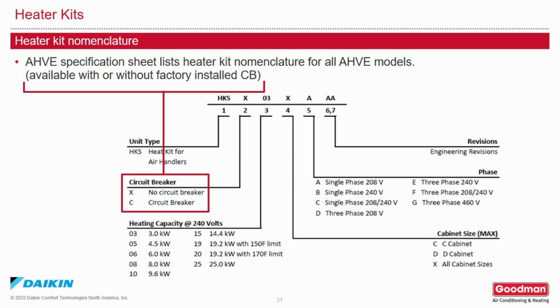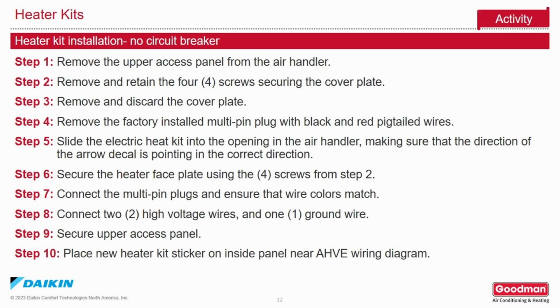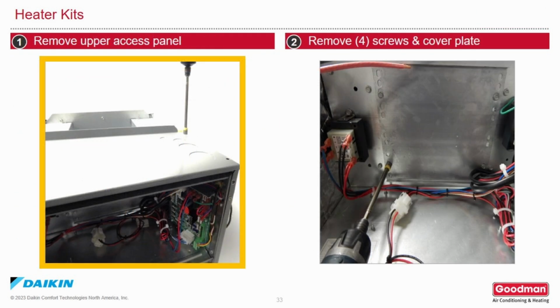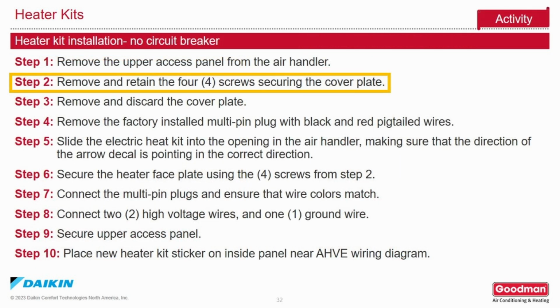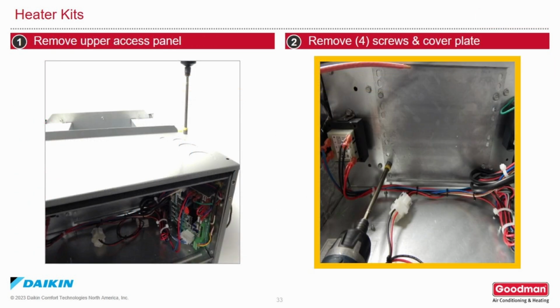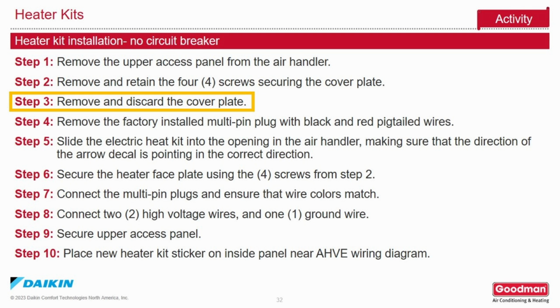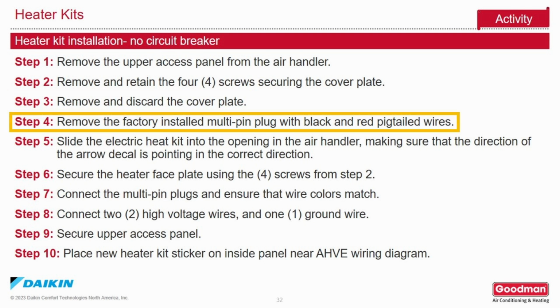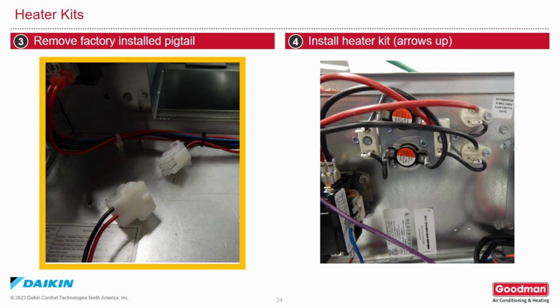Here's an example of the heater kit nomenclature. The specification sheet lists the heater kit nomenclature for all AHVE models. They are available with or without a factory installed circuit breaker. Heater kit installation with no circuit breaker. First, remove the upper access panel from the air handler. Remove and keep the 4 screws securing the cover plate. Remove and discard the cover plate. Remove the factory installed multi-pin plug with black and red pigtail wires.